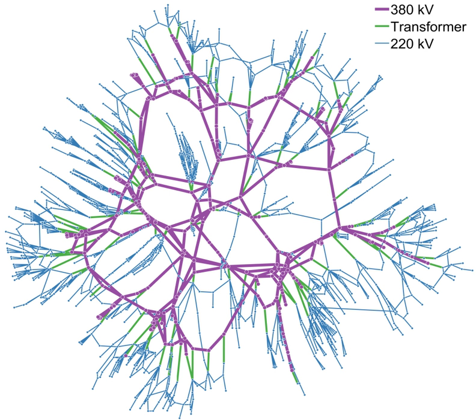Interconnections can be tied to each other via high-voltage direct current power transmission lines, DC ties, or with variable frequency transformers, which permit a controlled flow of energy while also functionally isolating the independent AC frequencies of each side. The benefits of synchronous zones include pooling of generation resulting in lower generation costs, pooling of load resulting in significant equalizing effects, common provisioning of reserves resulting in cheaper primary and secondary reserve power costs, opening of the market resulting in possibility of long-term contracts and short-term power exchanges, and mutual assistance in the event of disturbances.